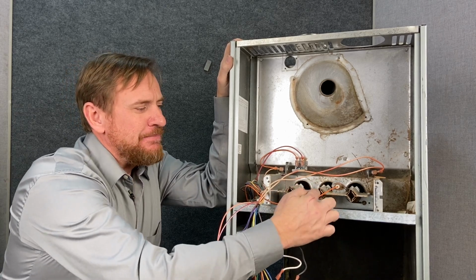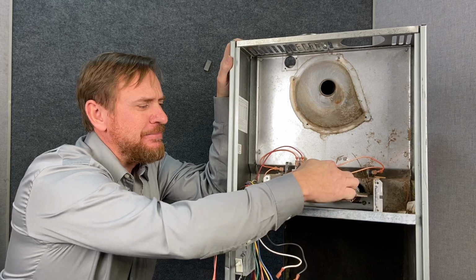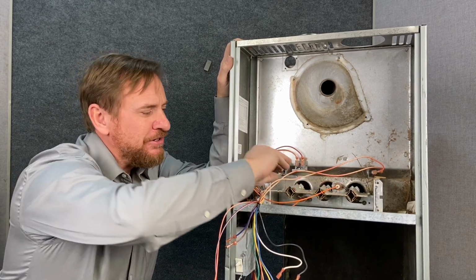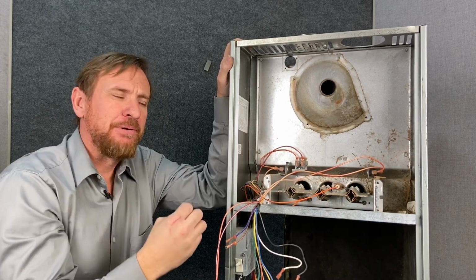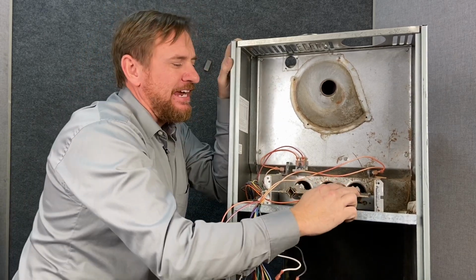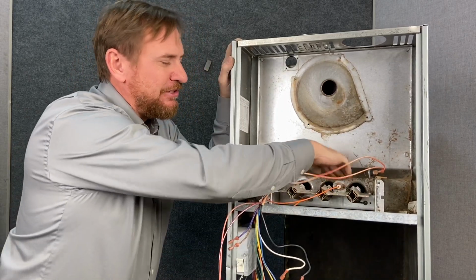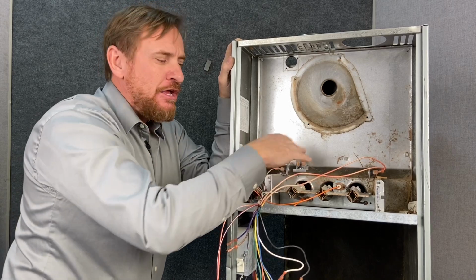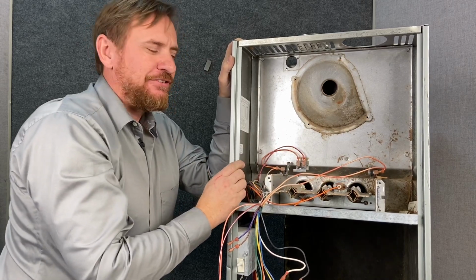So the gas shoots in the middle, and the primary air is coming in these little holes right here. And this burner's job is to mix the air and the fuel so it burns efficiently. So it's going to mix the air and the fuel inside the burner, and it aims it towards the holes in the heat exchanger in the back. Once we pull these pieces out, you'll get to see that soon.